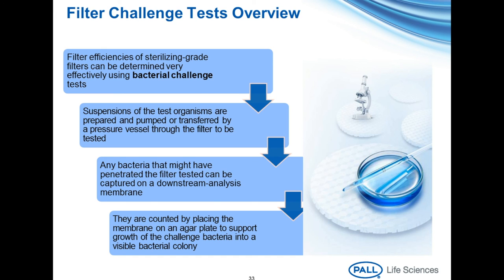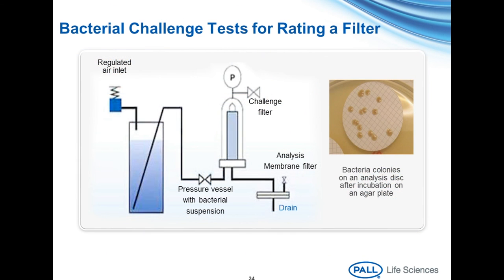For obvious and very necessary reasons, it's a very stringent test. Here's a cartoon diagram of a simple bacterial challenge test showing the vessel containing the bacterial suspension, the test filter, and then the analysis filter. This picture shows an example of bacterial colonies on an analysis disk post-filtration, post-incubation. It shows if any bacteria got through, they would grow on that analysis disk.